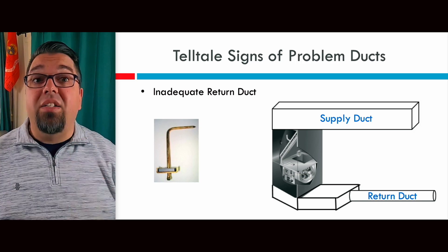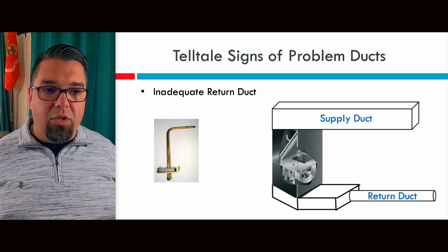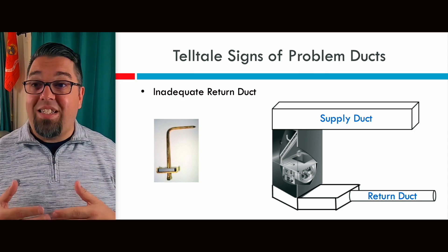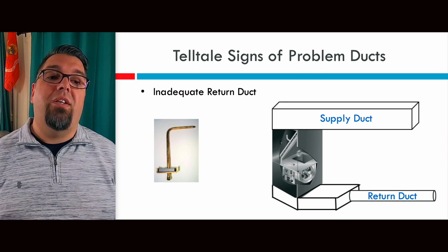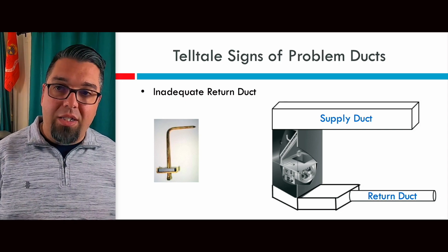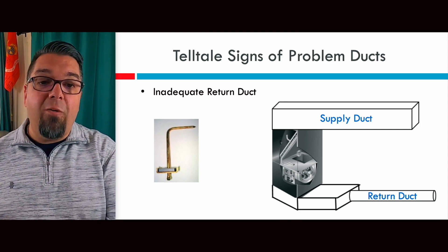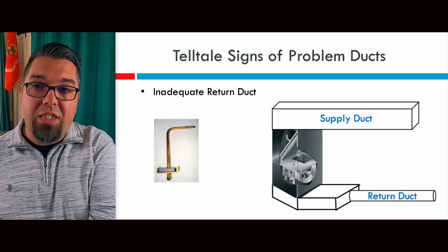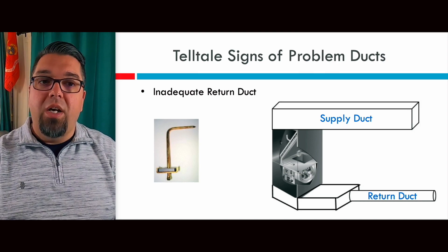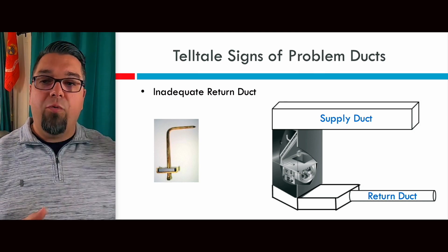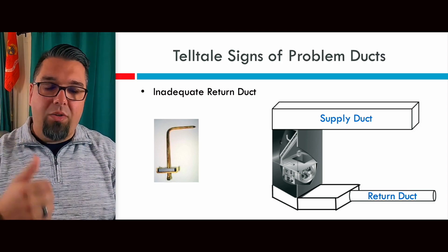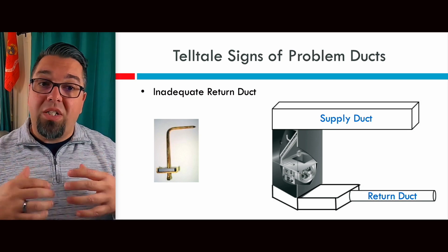Let's talk about some of the telltale signs of what you see out there with existing duct systems. The number one reason is inadequate return ducts — where the supply duct may be sized correctly, but the return duct is much smaller than it needs to be. We see this when you replace an inefficient older 80% furnace and put in a much higher-volume, high-efficient furnace, because now instead of that heat going out the flue pipe, it's actually going to need a bigger bus to deliver the BTUs to the space — not let it go outside. So you need more CFM when you do that.